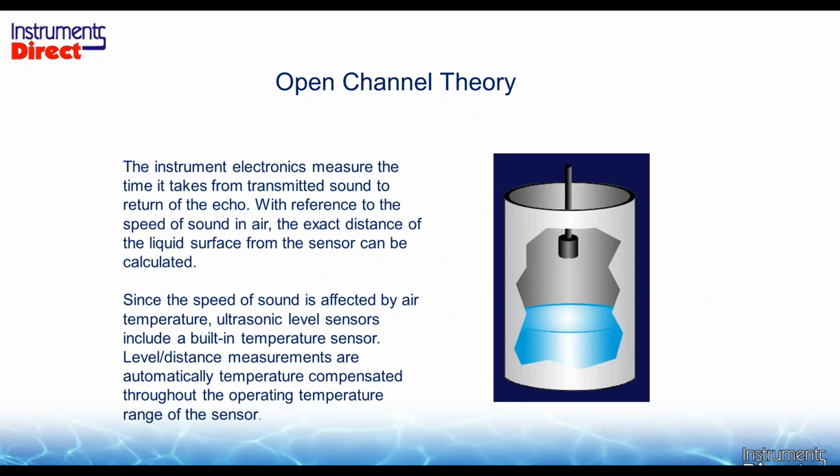And so we've derived different ways to use that technology. So the first method to use that technology is, instead of getting a ruler, let's use a non-contact device to measure that level. So step one, we need an ultrasonic level sensor. An ultrasonic level sensor, basically, again, kind of like radar, sends a sound beam from the face of the sensor and reflects off the liquid surface, comes back to the sensor, and from the time it takes we can calculate the level of the process liquid.